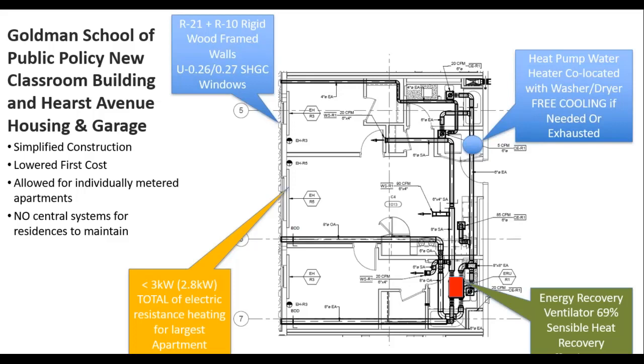But this is a strategy where we paired that individual tanked water heater right next to the washer and dryer exhaust, so that if it gets too cold in that space, we can exhaust that cold air. But we've got free cooling in the summer, so we didn't technically put in active cooling, but we've got some supplemental cool that comes off the domestic hot water tank. So that's my ethical use of electric resistance heating.